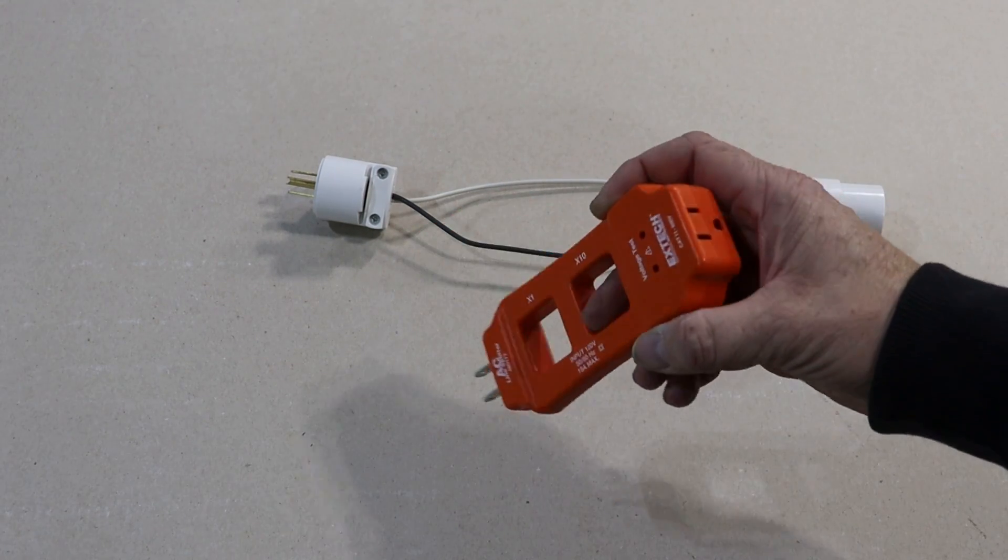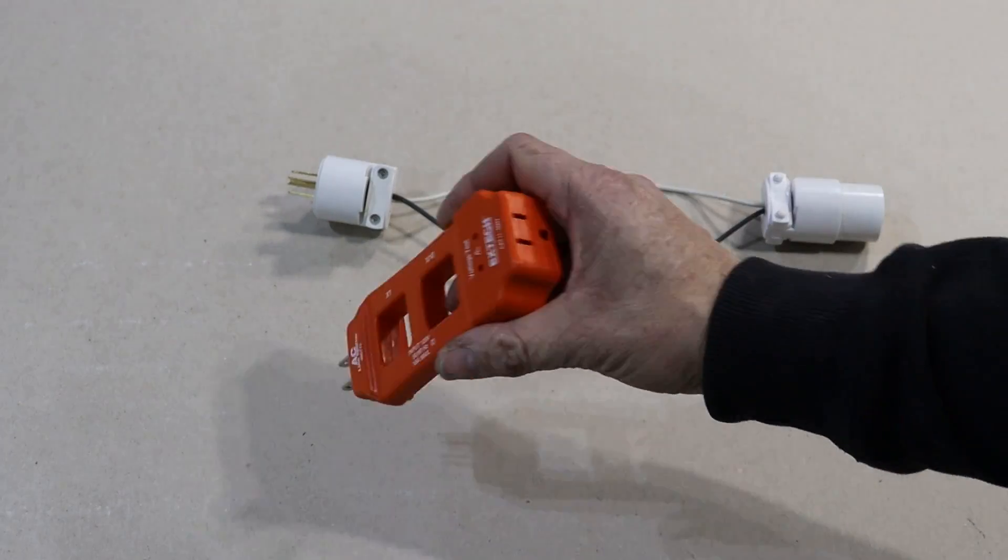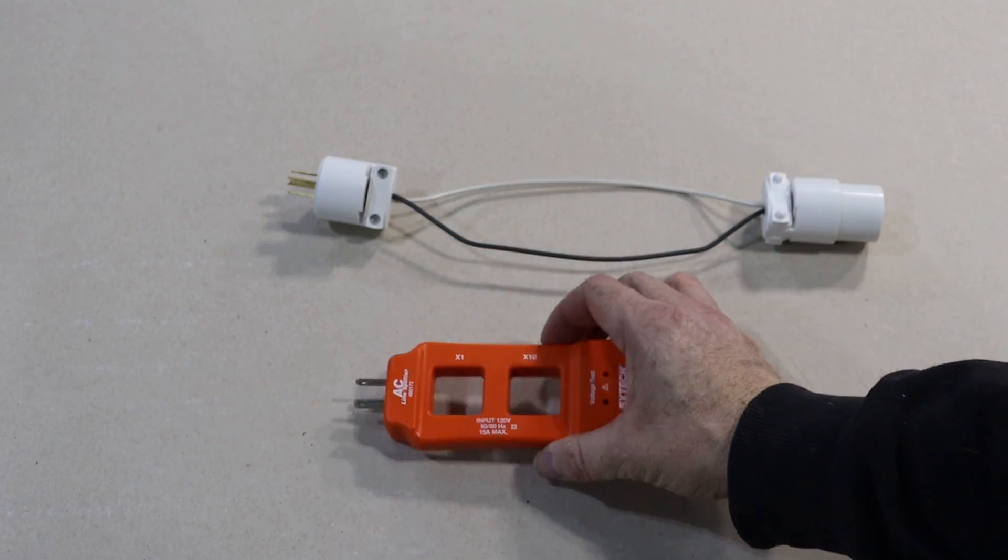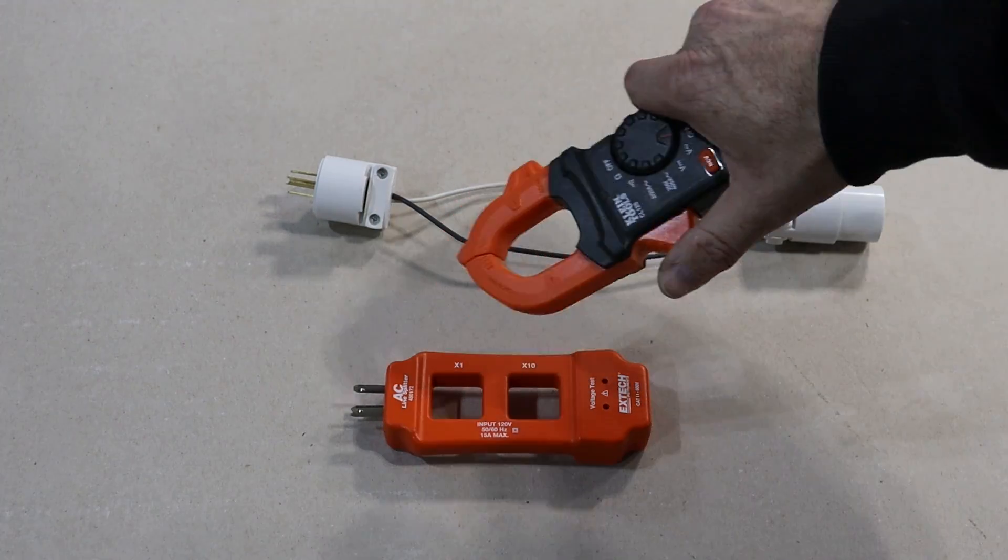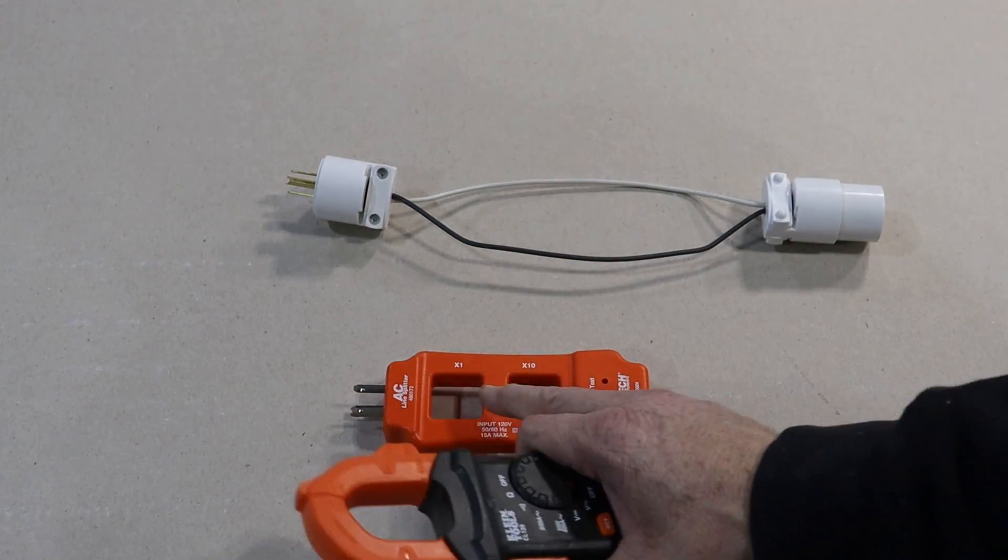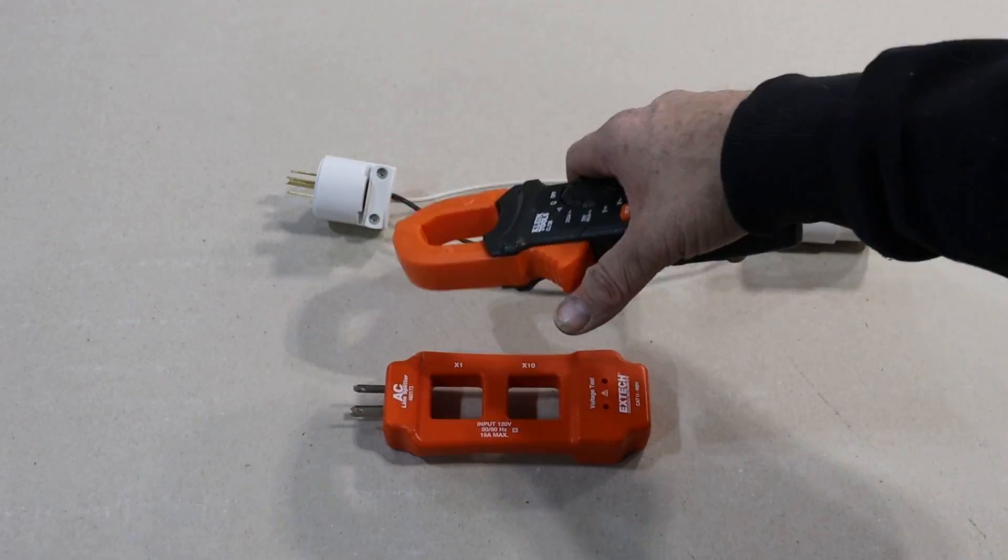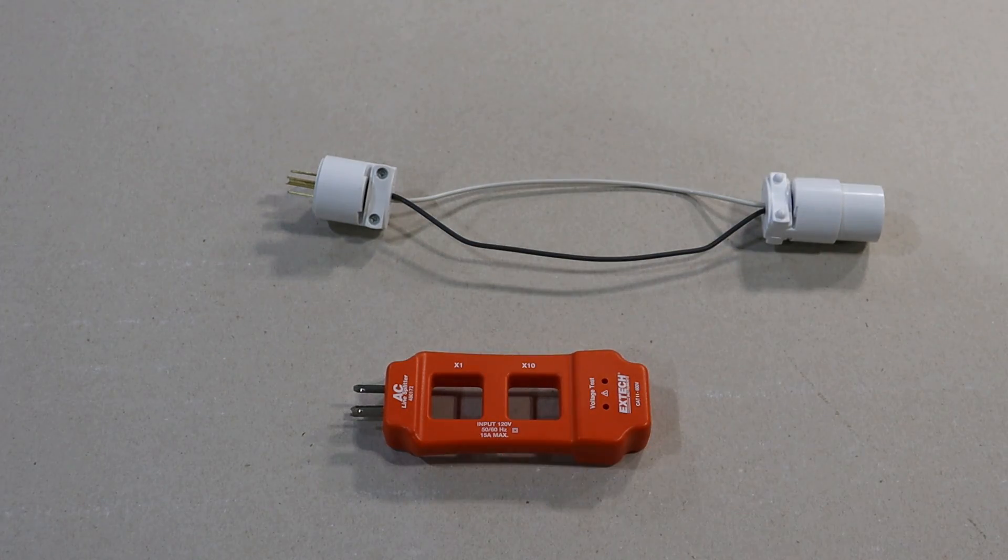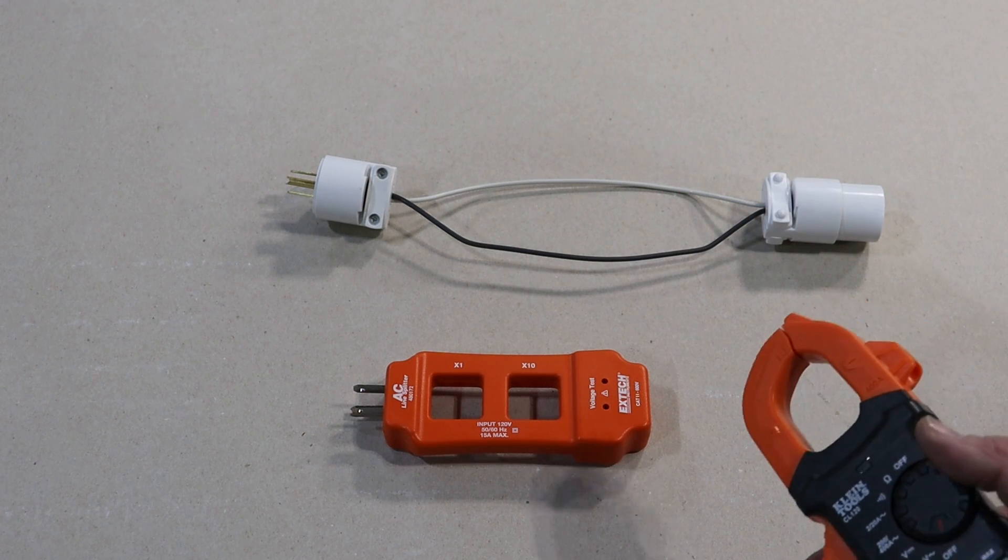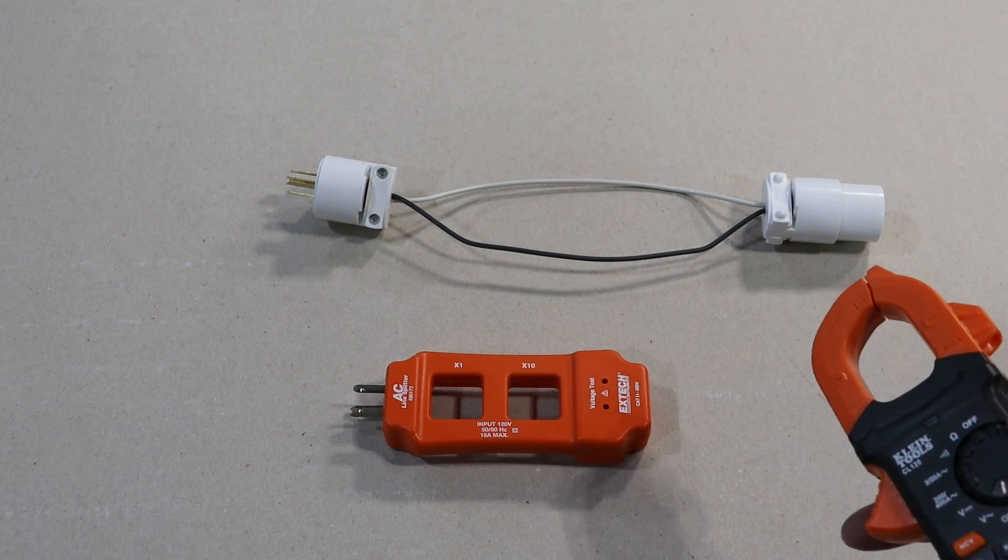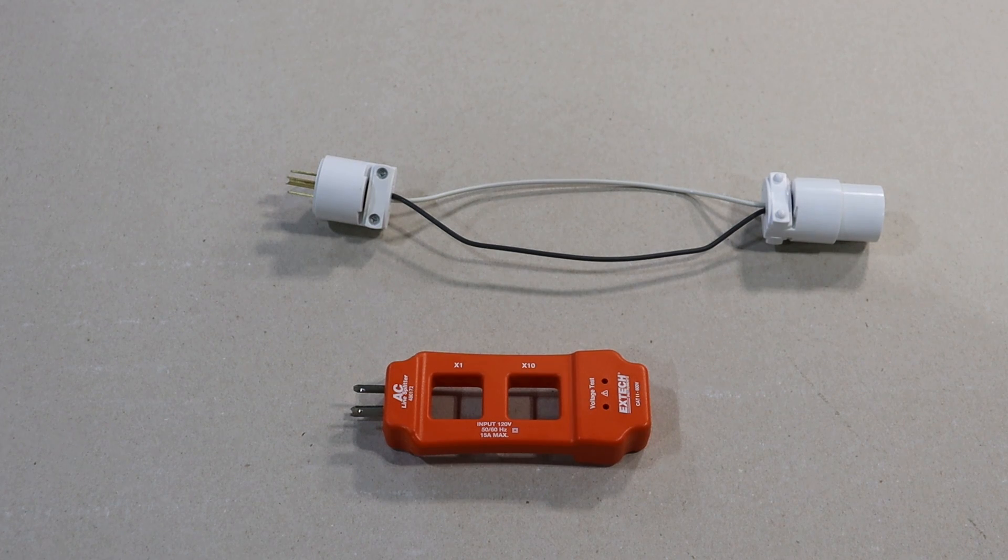Obviously the safest way is to go buy one of these AC line splitters. You just plug it into an outlet, plug in your device, and then when you're running your device, you can clamp on either one of these openings here. There is a couple of different ranges. I'd want to use the times one range, but this is a 15 amp max unit, and I don't want to use this line splitter because I already know that the jackhammer draws more than 15 amps.